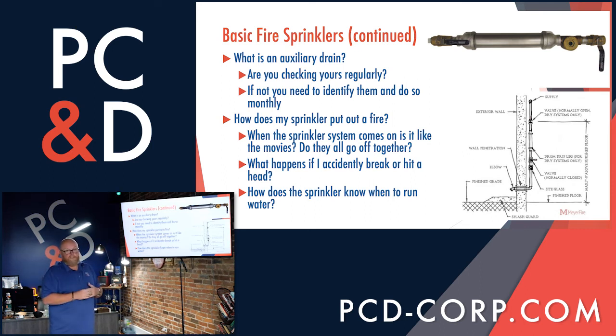You probably have seen this on your car. You may check your car's air pressure sitting still in the morning before you ever drive your car. You may have a PSI of 35. You get out and you start driving down the road. As that tire starts to heat up, that heat affects the air on the inside of that tire. What happens? The air on the inside of the tire begins to expand, because when air gets hot, air expands. As that air gets warm and it expands, the pressure goes up. Very similar in our attics.